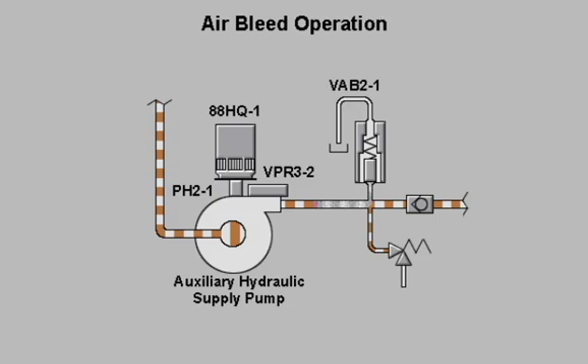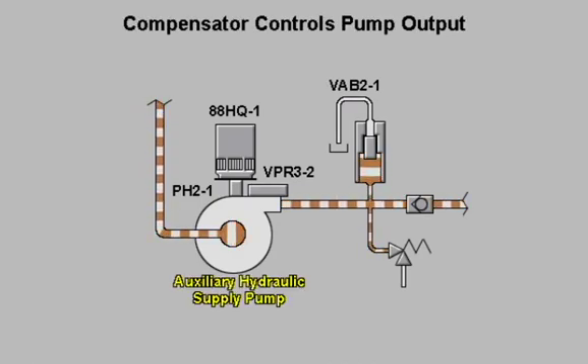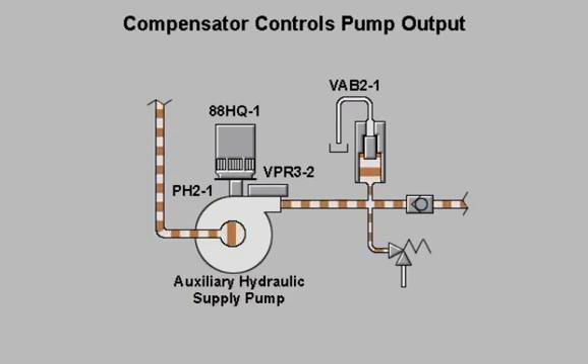When the auxiliary hydraulic supply pump is started, any air trapped in the pump discharge line will escape through air bleed valve VAB 2-1. Increasing oil pressure in the hydraulic supply manifold will quickly close the air bleed valve. The auxiliary hydraulic supply pump will deliver a maximum flow of oil to the hydraulic supply manifold until the pressure setting of the compensator VPR 3-2 has been achieved.